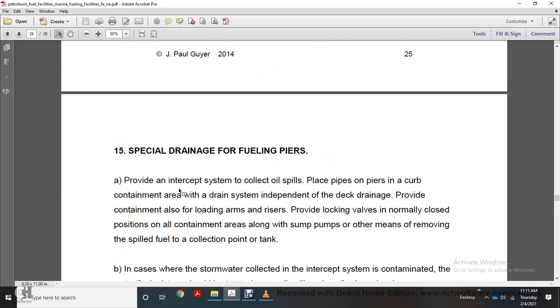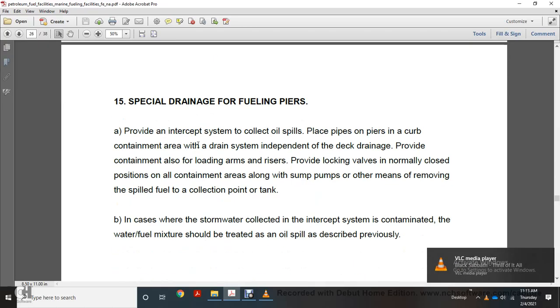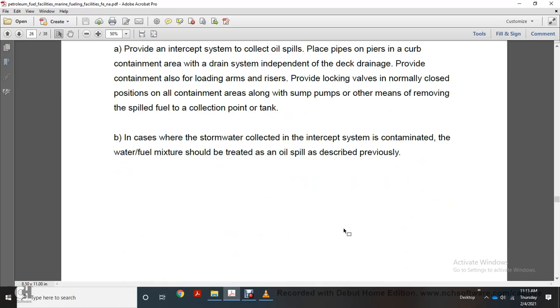15. Special drainage for fueling piers. Provide an intercepting system to collect oil spills, with a curb around the pier and a contaminated drain system independent of the deck drain. Provide contaminated drainage also for the loading arm and the risers. Provide locking valves, normally closed, on contaminated areas, along with a sump pump or other means of removing the spilled fuel to the collection point or tank. In case stormwater is collected by the intercepting system, the contaminated water-fuel mixture should be treated as an oil spill, as described previously.